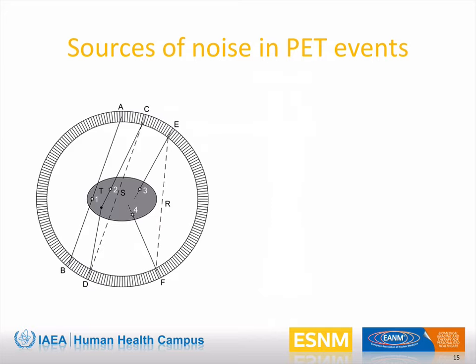Let me clarify here that the term noise in PET is often inappropriately used to describe the fluctuations in space in the measurement of a uniform activity. A more appropriate definition is the image roughness, that is usually measured in terms of the standard deviation of the measured value.